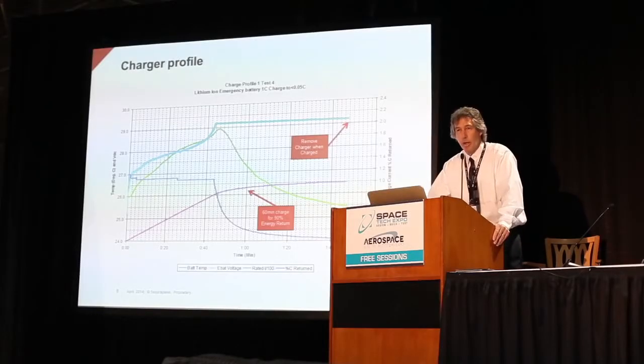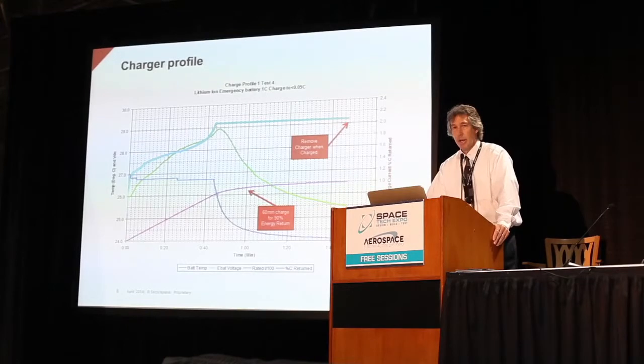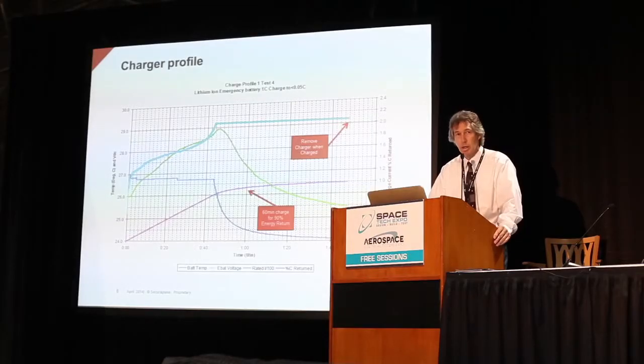Charging profiles are one area that I believe can still use some research in lithium batteries. Lead-acid chargers have been around for so many years and have so many different capabilities, from bulk charging to topping to trickle charging. But most lithium cell providers request that their cells be charged in a two-stage approach: constant current, and then constant voltage. Such a two-stage methodology is employed in the Securaplane batteries.